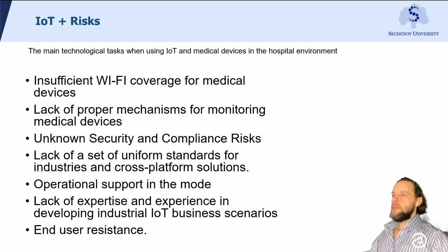There is a huge question about how to check medical devices which are not provided by a medical organization, but which are in individual use by the patient, because all medical devices go through regular checkups, and we need to be sure that they measure correctly, work correctly, and are up to date. And in the case of personal devices, there is no process of medical device control or some tests for them.